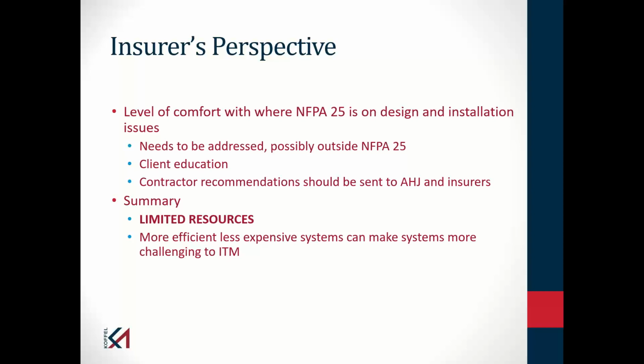And here's the last piece in this particular case that was damaging, because the fire marshal, the same person who approved the plans without the sprinklers in the sauna, stated in his deposition, well, if the contractor had put that note on an inspection report, I would have gone into the building and told them that they had to put sprinklers in the sauna. You kind of see where the contractor came out on the losing end of this, which was fully expected because a similar case had already gone to the Supreme Court in New Jersey, and they ruled that we don't really care what 25 says. Contractor's the expert. You should have alerted the owner. But that's New Jersey. Again, NFPA 25 doesn't require that.